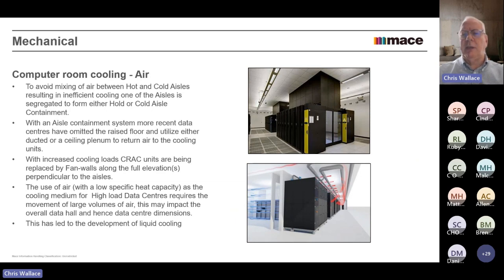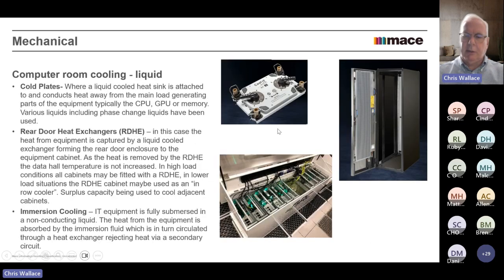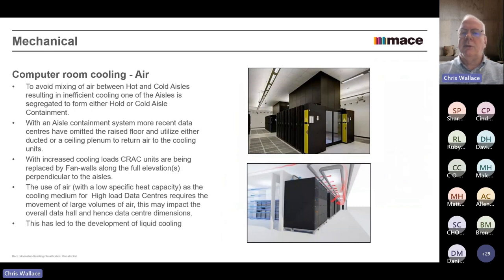So what people started doing is containing one or the other aisle, and the terms hot aisle or cold aisle containment were derived. This top figure is basically aisle containment. I'm not sure whether it's hot aisle or cold aisle. It's actually hot aisle when I look at it, and hot aisle is probably the most common. So the cold air is coming through all these grids. You see the series of three floor grilles there. That's the cold air coming into the front of the cabinets, and on the other side there's some cold air coming into the other cabinets, and the hot aisle is all going straight out into that chimney, back into the ceiling area, and then it's directed over the ceiling void back to the terminal cooling unit, where it will get cooled and then sent back out again.